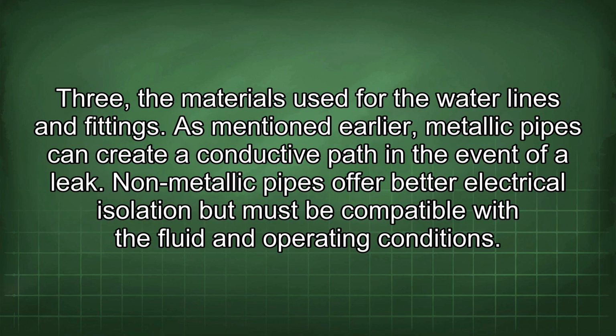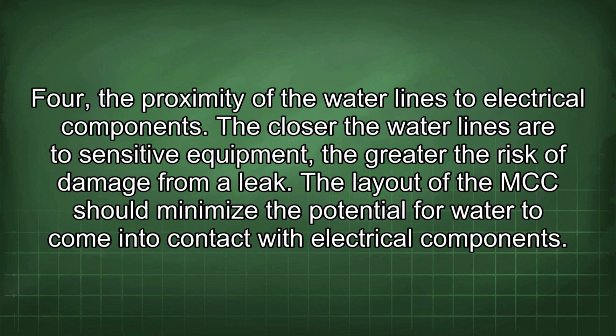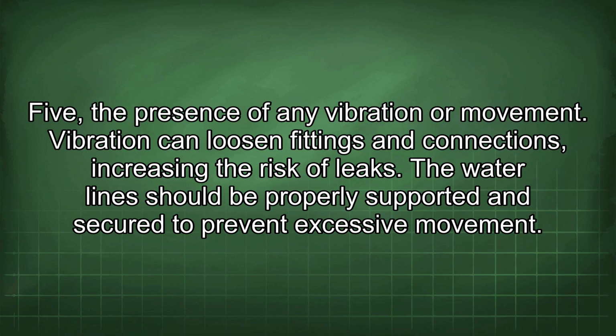3. The materials used for the water lines and fittings. As mentioned earlier, metallic pipes can create a conductive path in the event of a leak. Non-metallic pipes offer better electrical isolation, but must be compatible with the fluid and operating conditions. 4. The proximity of the water lines to electrical components. The closer the water lines are to sensitive equipment, the greater the risk of damage from a leak. The layout of the MCC should minimize the potential for water to come into contact with electrical components. 5. The presence of any vibration or movement. Vibration can loosen fittings and connections, increasing the risk of leaks. The water lines should be properly supported and secured to prevent excessive movement.